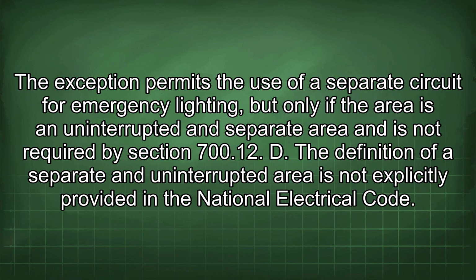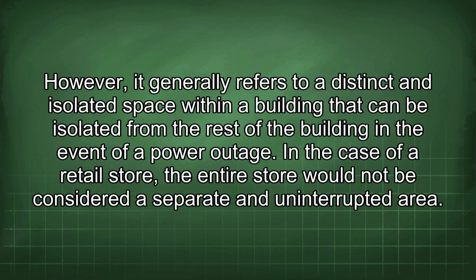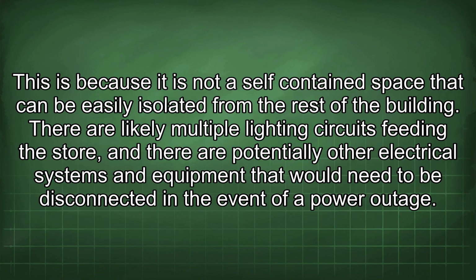The definition of a separate and uninterrupted area is not explicitly provided in the National Electrical Code. However, it generally refers to a distinct and isolated space within a building that can be isolated from the rest of the building in the event of a power outage. In the case of a retail store, the entire store would not be considered a separate and uninterrupted area. This is because it is not a self-contained space that can be easily isolated from the rest of the building. There are likely multiple lighting circuits feeding the store, and there are potentially other electrical systems and equipment that would need to be disconnected in the event of a power outage.